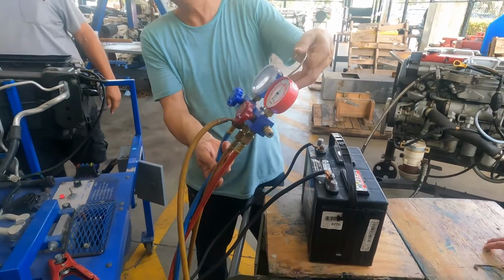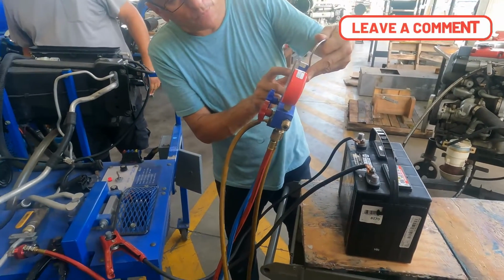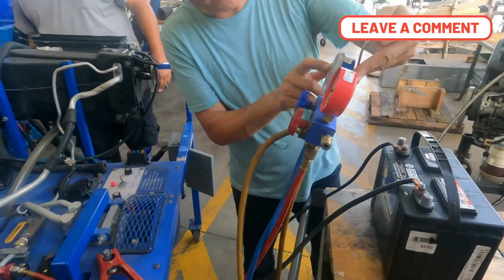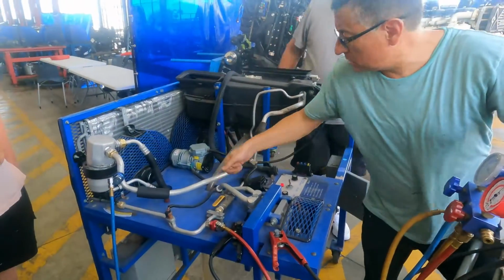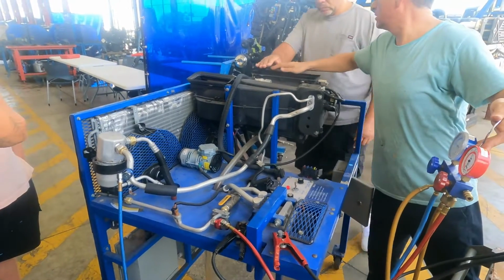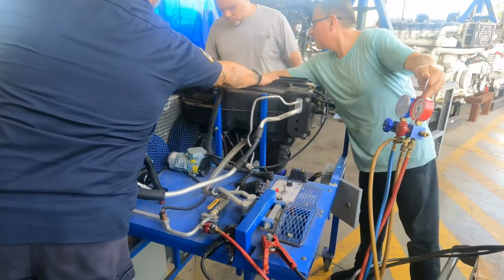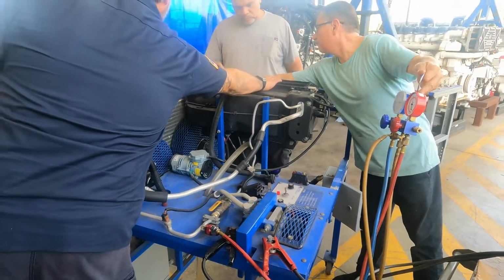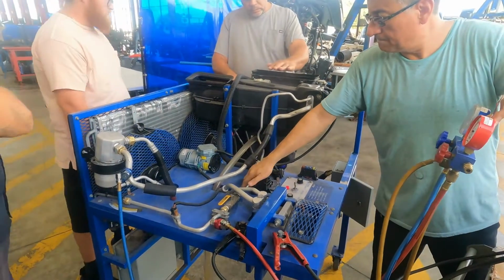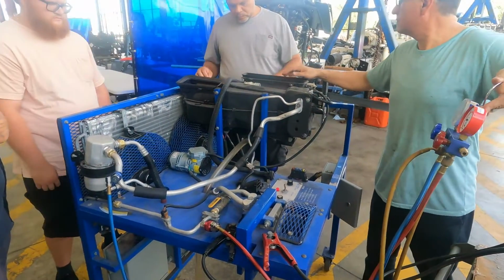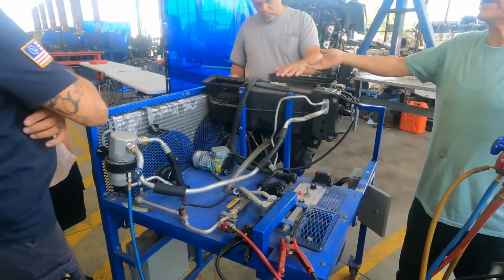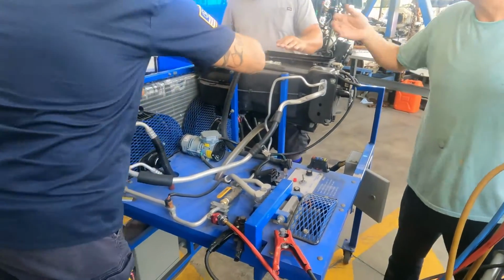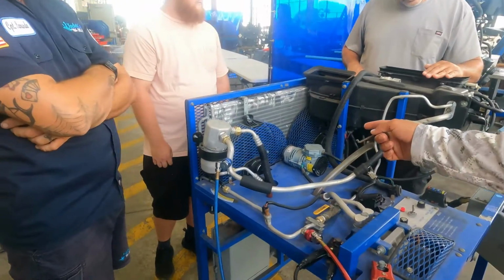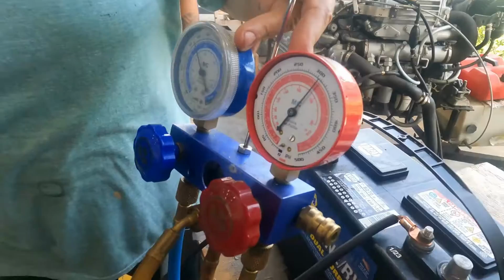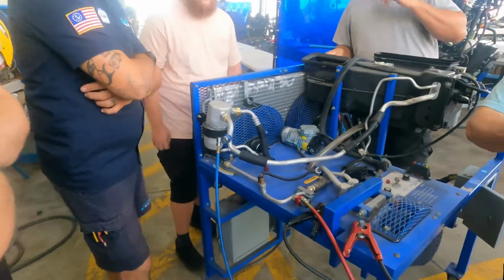That's okay. And now the pressure here in the low pressure side is around 25. It's a little low. Now it's better. Turn back. Stop that. That's the problem. Once again, the pressure goes up immediately.